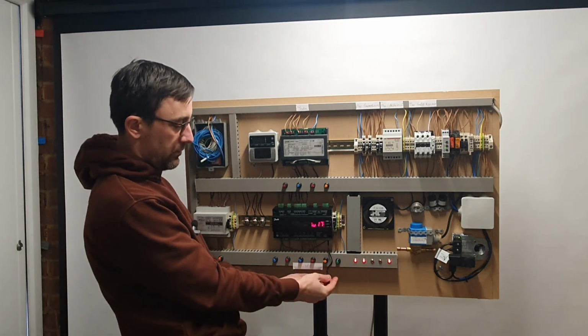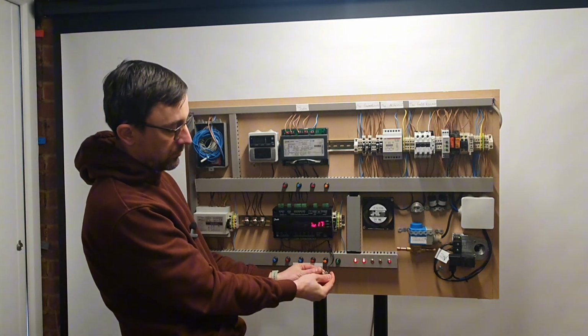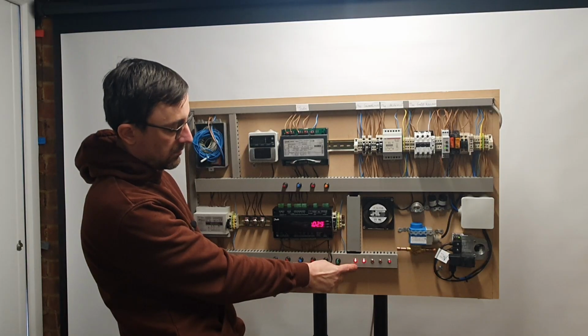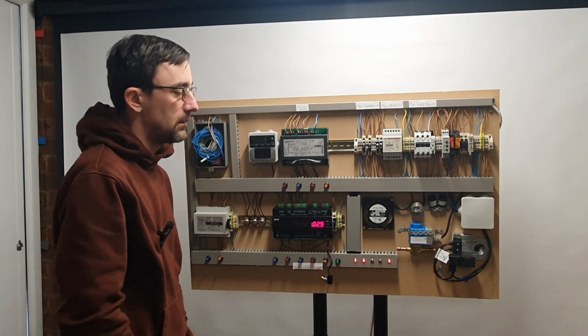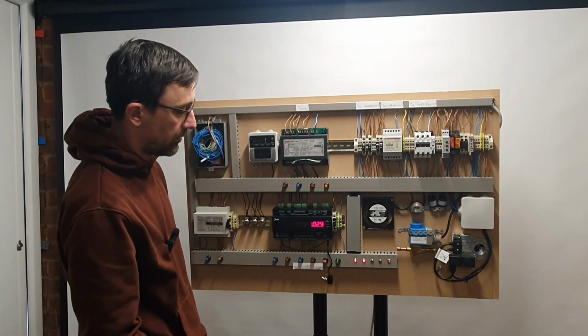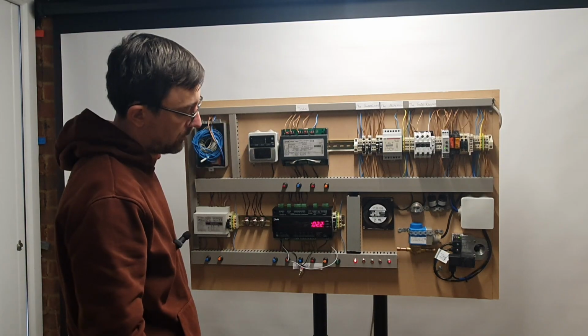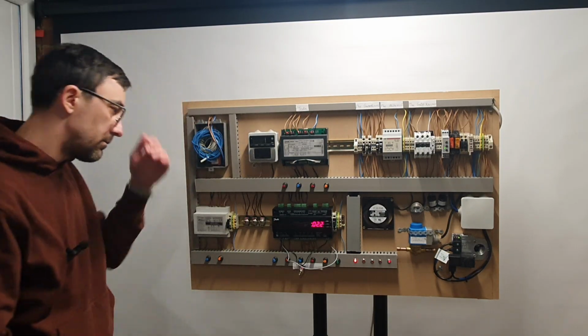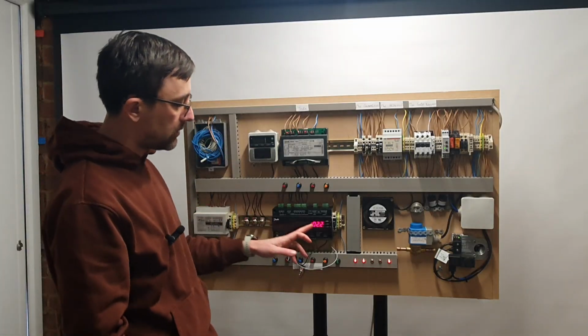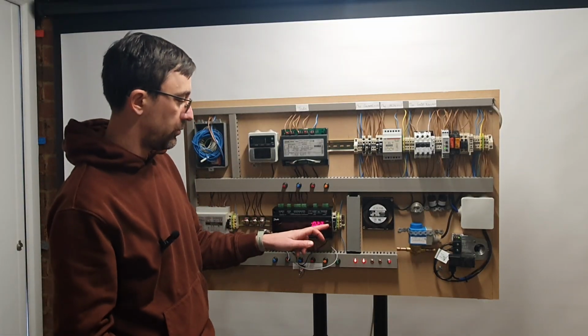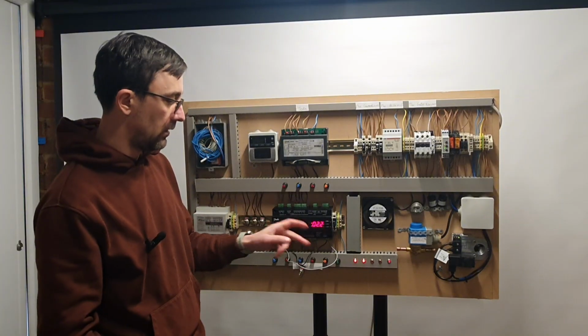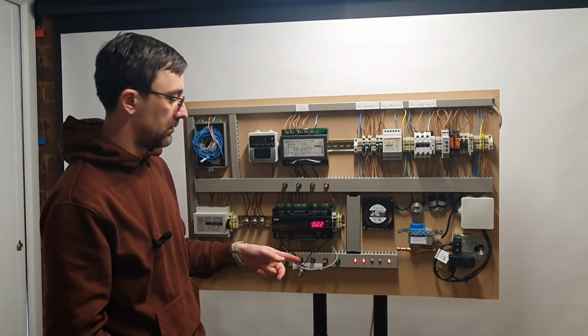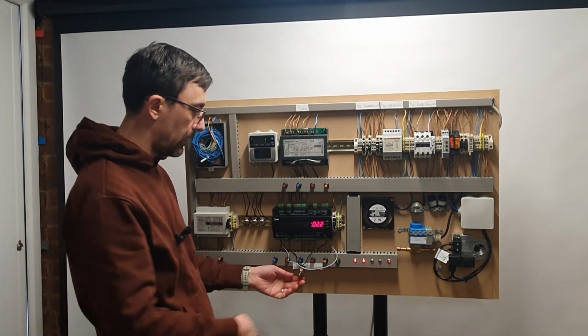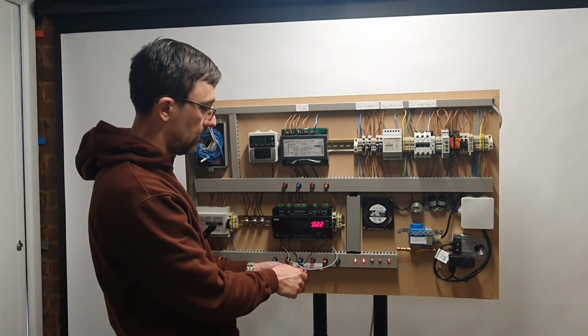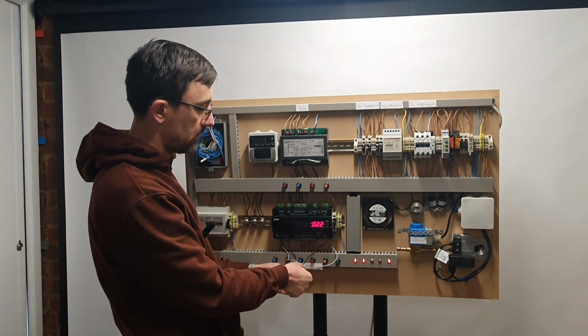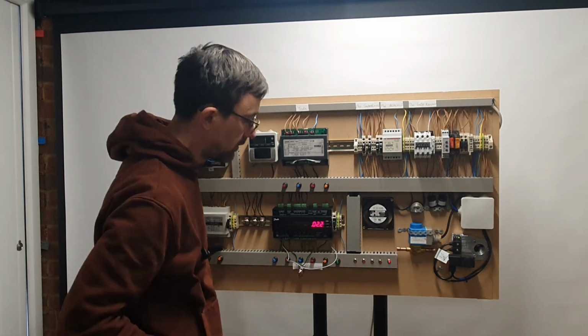So if I switch to band number 2, that should stop. Done. Stop. Now I'm in thermostat band number 1. The temperature is 2.2 degrees. Set point is 0. You want it to start cooling down. Move to the second band of thermostat, which has a set point of 3.5, and it will stop.